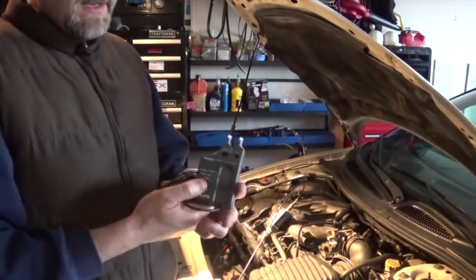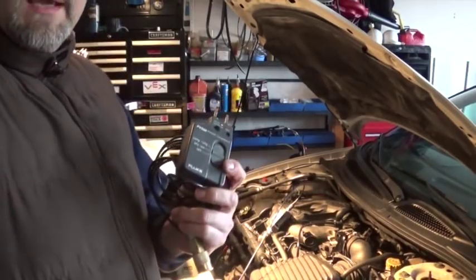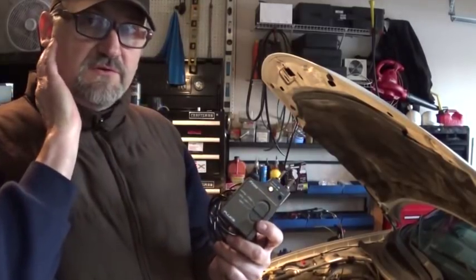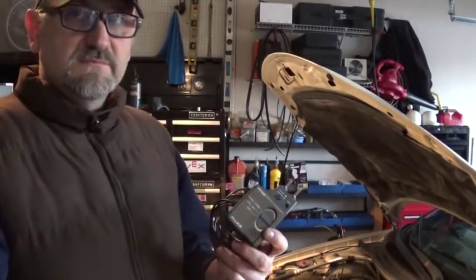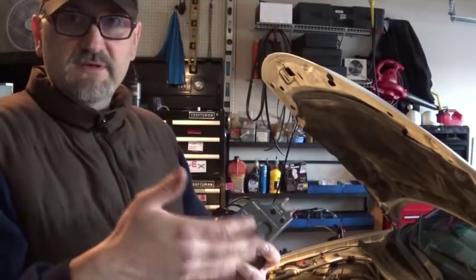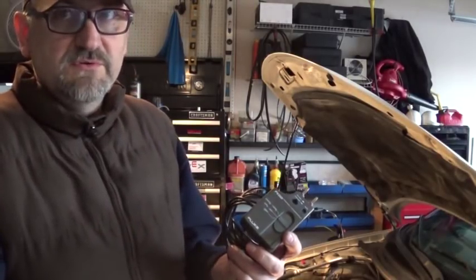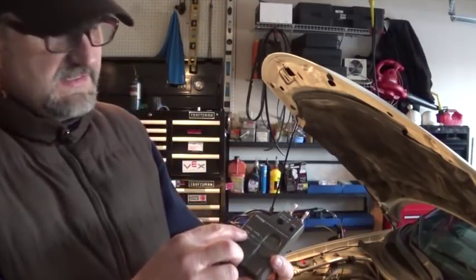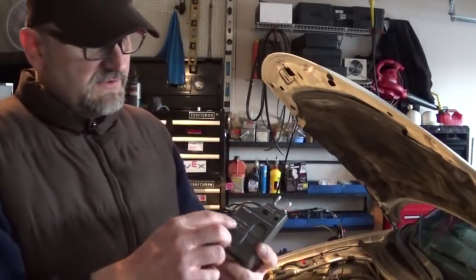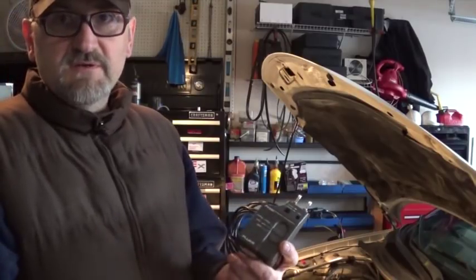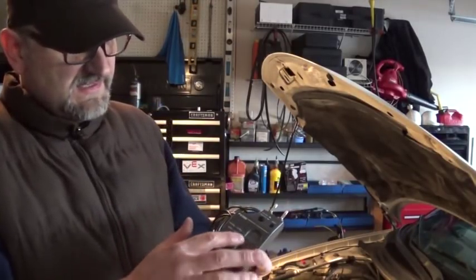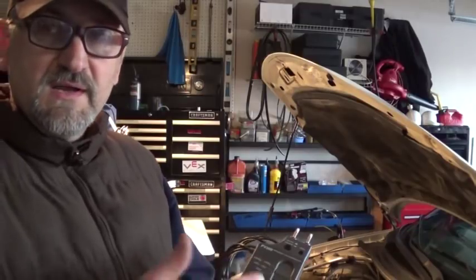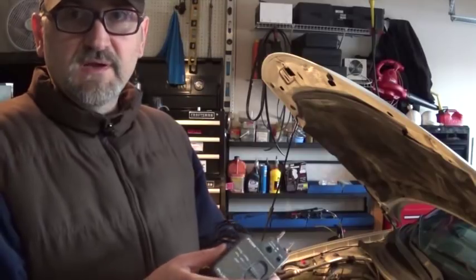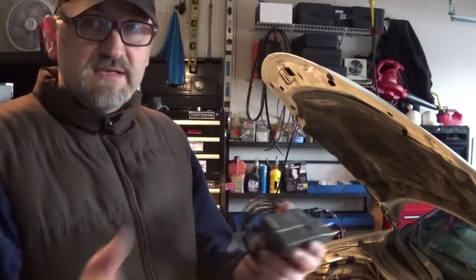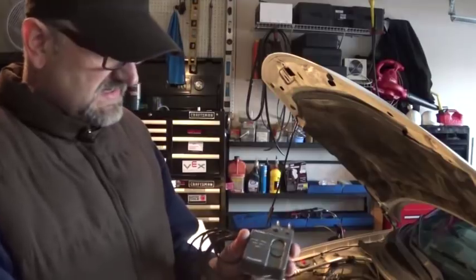And so it is very nice if you don't have a Pico scope. Honestly, you don't need a custom probe or something like that. It's simply just looking at the millivolts. You get automatic conversion to pressure, to PSI, and the same with kilopascals. When you set the range for kilopascals, 1 millivolt is going to be 1 kilopascal. It's the same thing with inches of mercury, 1 millivolt is going to be 1 inch of mercury. So you can really measure vacuum or negative or positive pressure pretty easily on any scope. It's a very nice feature on this FLUKE.